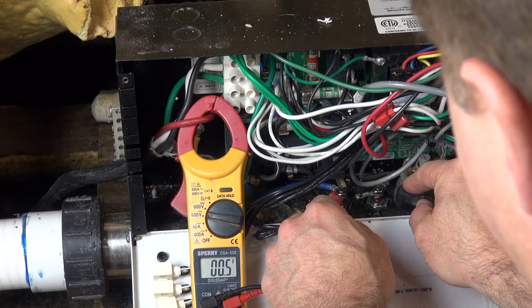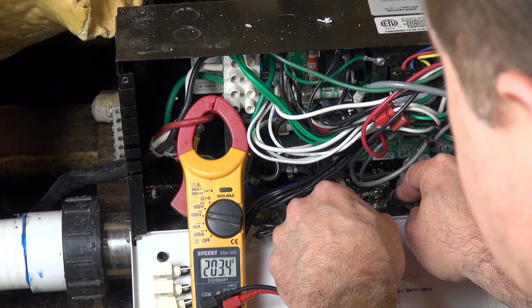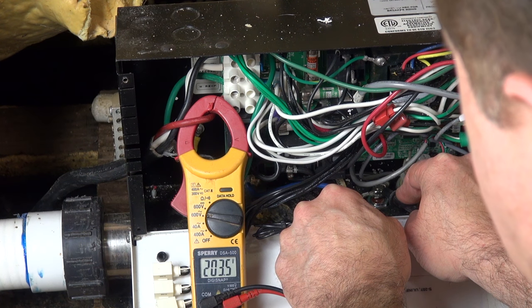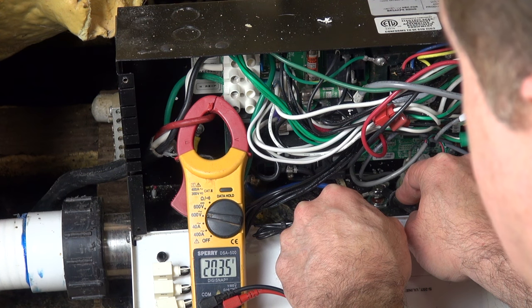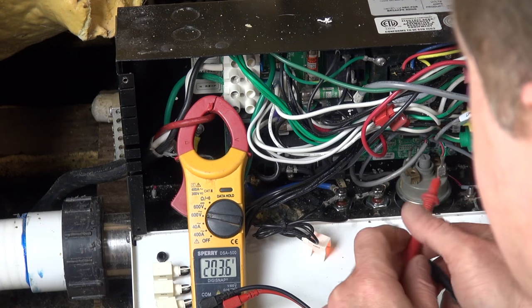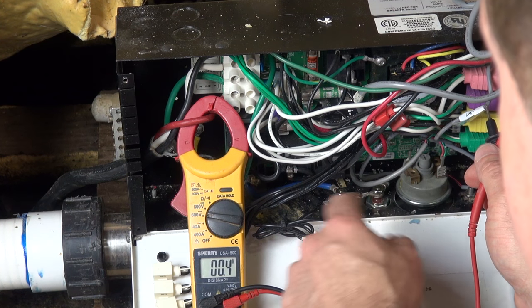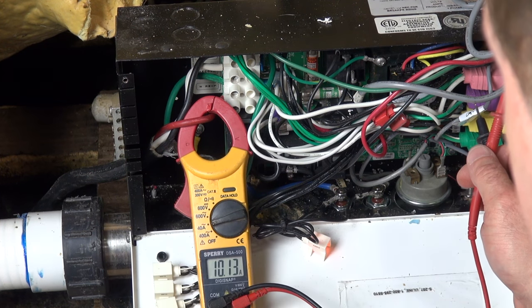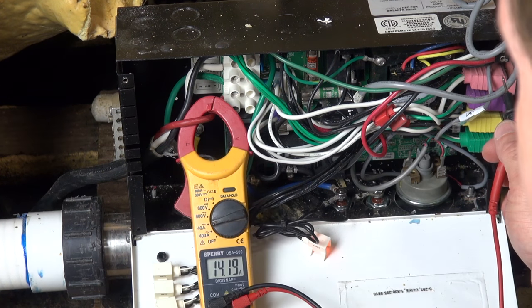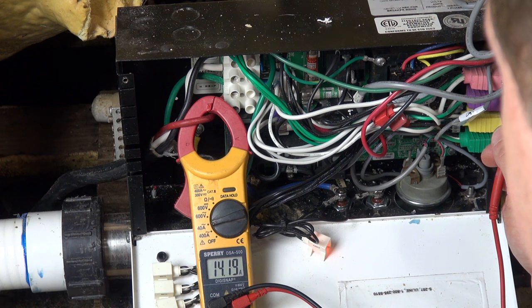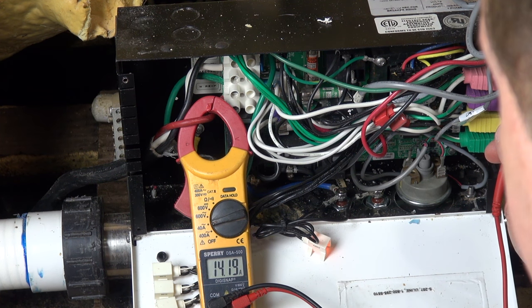You can also test here. You can verify that you have voltage across it. You can see that I'm 203, which I'm in industrial. I'm not at a home. I'm in industrial voltage, which is a little bit less. You can see it's showing 203. That does not mean that the heater is actually heating. The true test is, is it drawing current? Because you could theoretically have voltage here, but the heater be open and you're not drawing current. So there you go, friends. Another heater installed and working. No breaker trip. So we've got another hot tub working, friends.